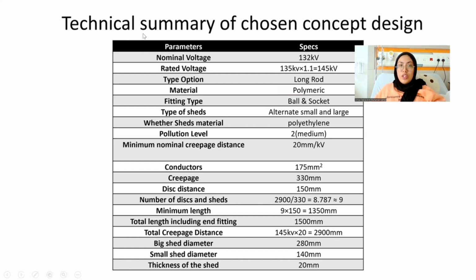For the parameters: our nominal voltage is 132 kV, rated voltage is 145 kV, type option is long rod, material is polymeric, fitting type is ball and socket, type of sheds is alternate small and large, weather shed material is polyethylene, pollution level is 2 (medium), and minimum creepage distance is 20 mm per kV.